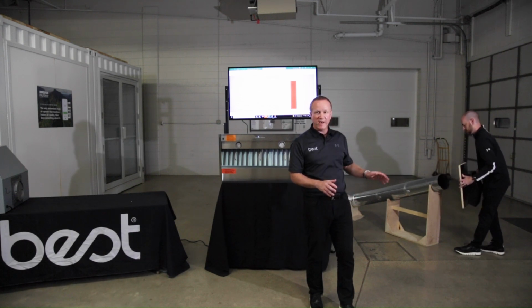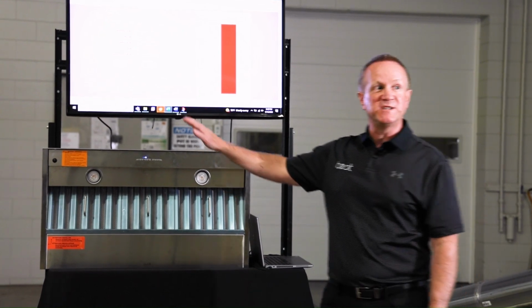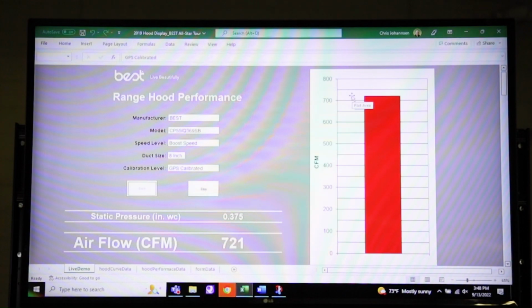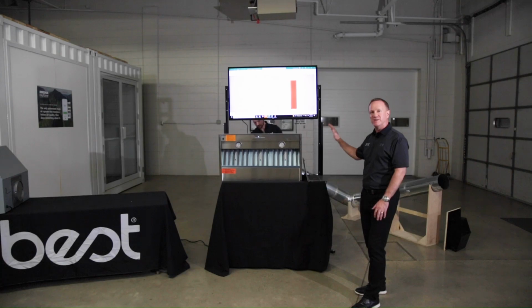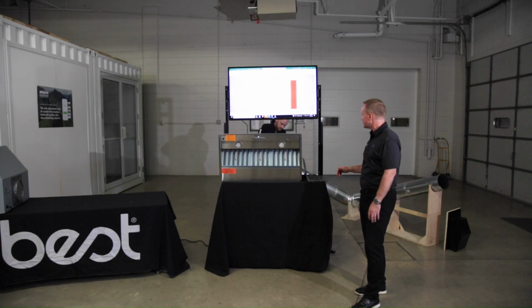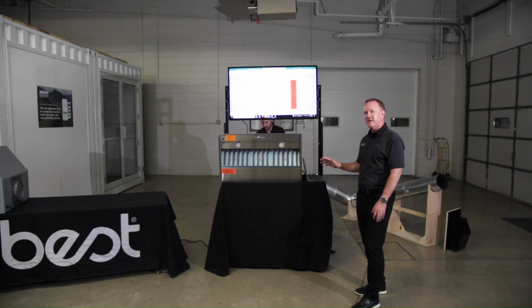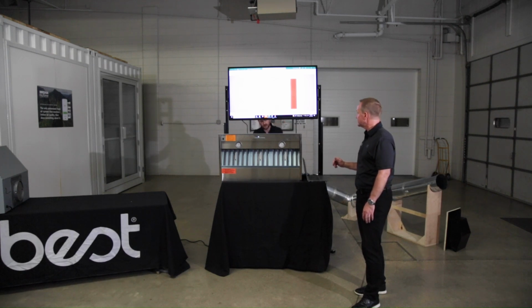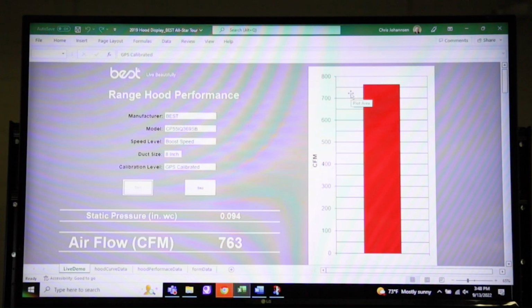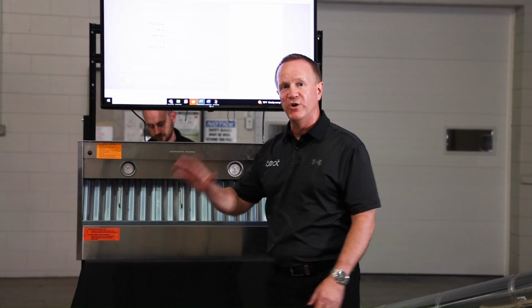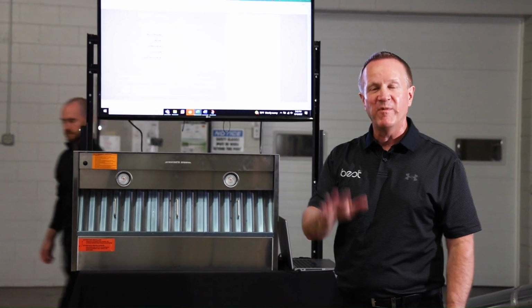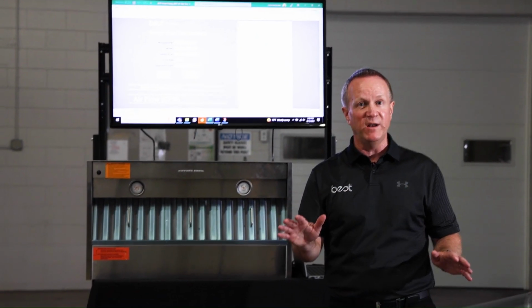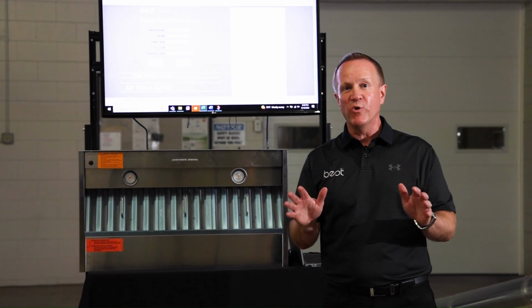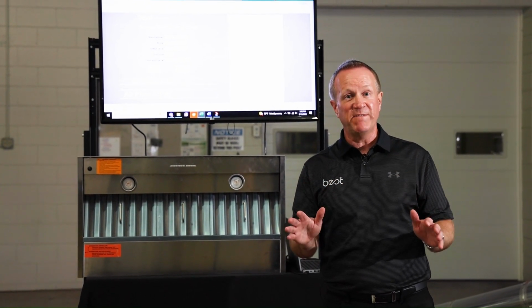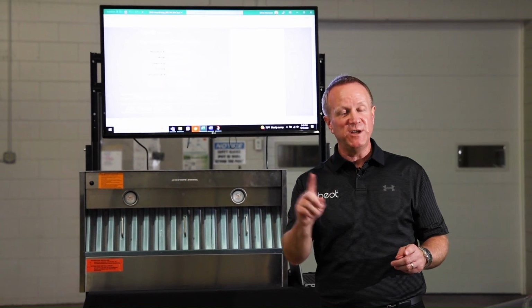We're going to take off our roof cap, and you can see we're already up to 720 CFM. And now my colleague is going to take off our additional ducting, and we'll see exactly how we're performing. So we're now performing at 760 CFM. So I'm actually going to turn our hood off. So we went from 530 CFM non-calibrated, that we went through and calibrated, we were performing at 650 CFM. That's full power. That's the guaranteed performance system.